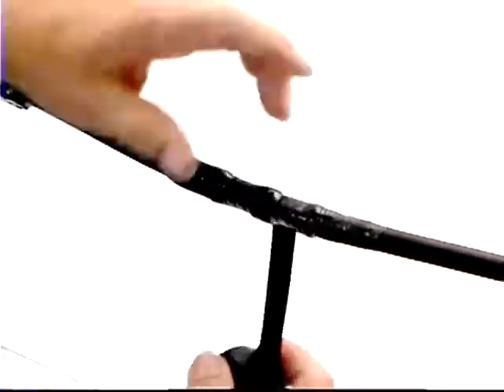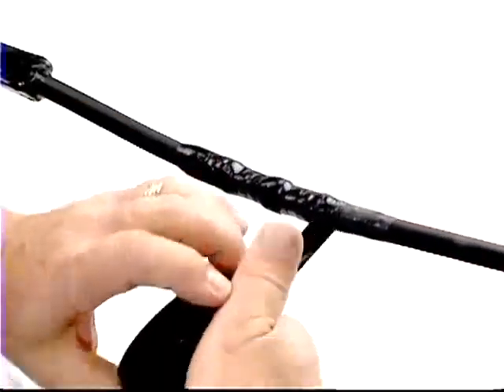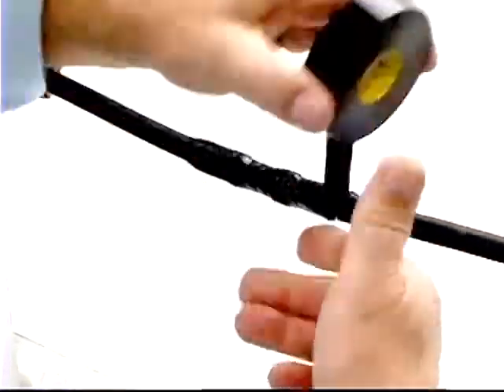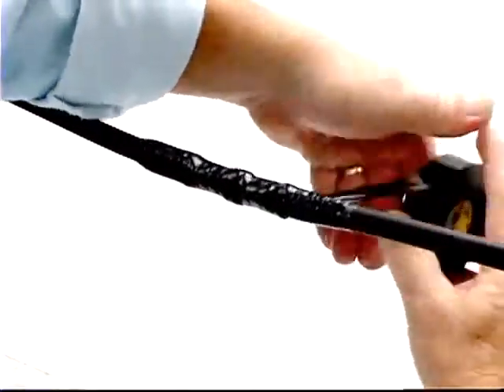Wrap the vinyl tape as you did the rubber tape, half-lapping it with moderate tension just past the edge of the rubber tape on the cable jacket, at least an inch onto the cable jacket. Wrap a minimum of two layers of the vinyl tape in this way.